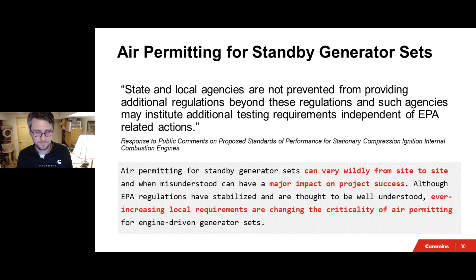One of the most common challenges we see today, and again, I'm going to pick on the West Coast as well as that Northern Virginia area and some other areas in between, is a huge focus on NOx emissions. There's typically a tonnage limit based on the given site, could be 100 tons a year of maximum potential to produce NOx emissions based on the number of engines on site. And with a standard Tier 2 product for an emergency engine, that target can be challenging to meet. And so we'll often see an SCR installed on those products in order to reduce NOx significantly. A well-sized or appropriately sized SCR can reduce NOx easily by 90+%.